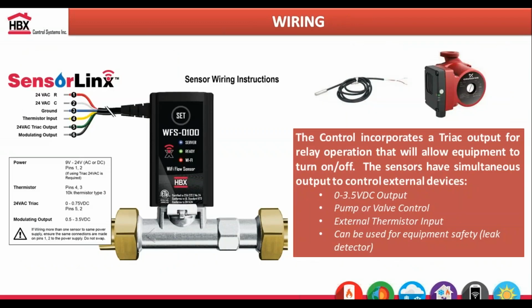In terms of wiring, it's 24 volts just to power up the sensors. You have the capability of using thermistor options. So if you want to use this as a regular flow meter, you just need one of these sensors, and you can get the temperature from your domestic hot water tank. You can put a thermistor right into the tank, connected to that flow sensor.